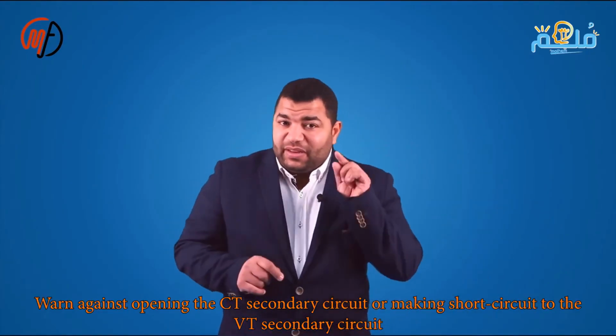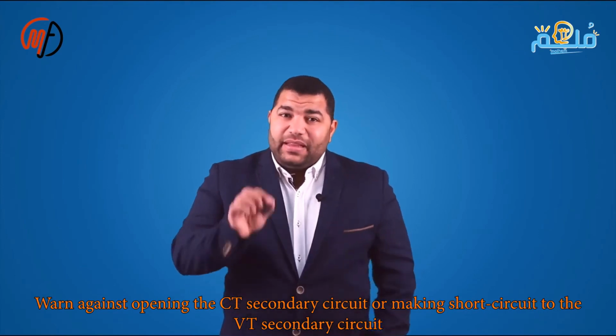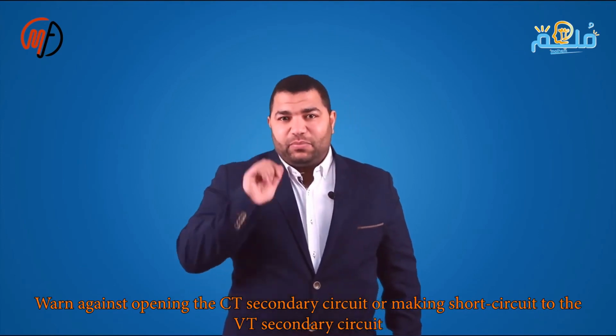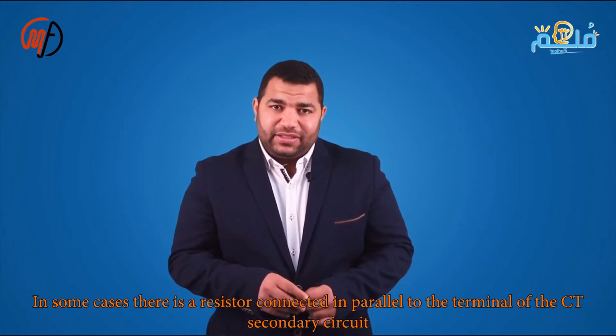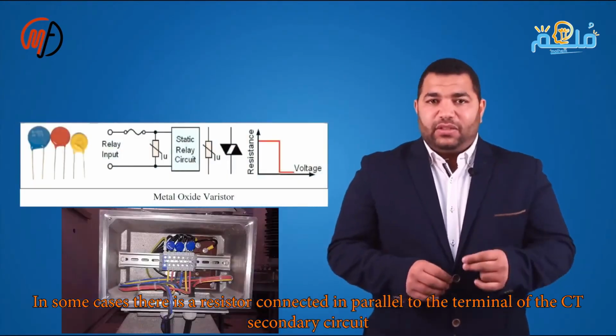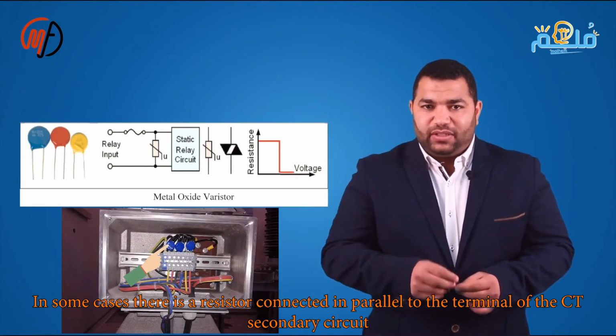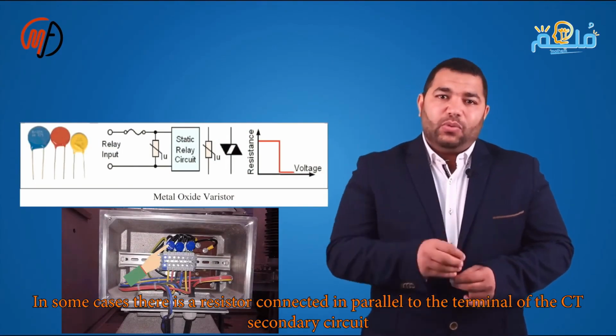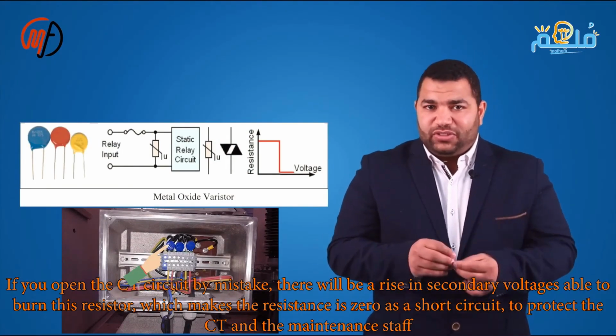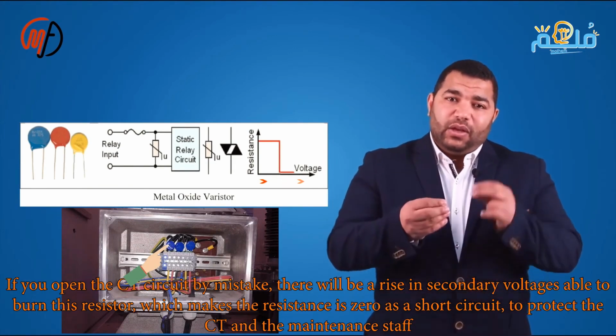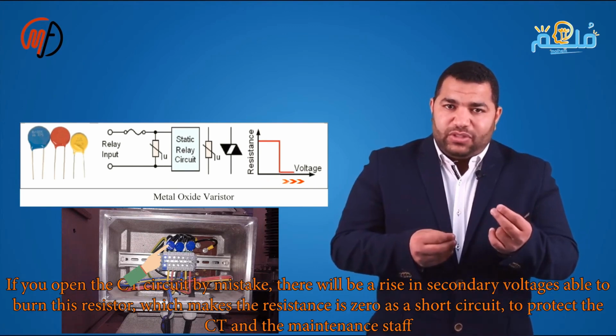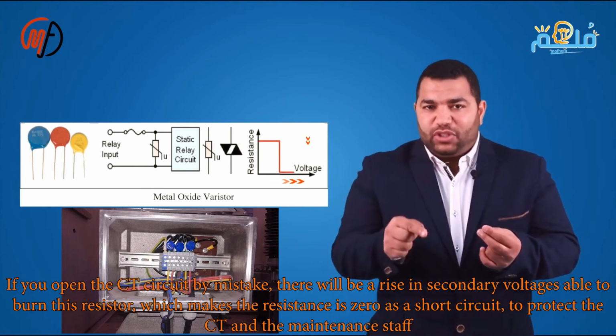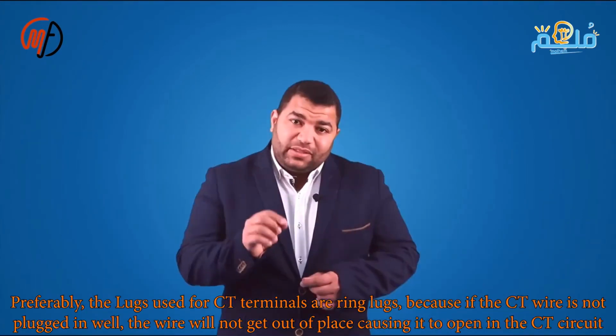A resistor parallels the CT secondary circuit for all phases. If opened, the voltage rise blows the resistor, shorting to protect the CT. Prefer ring lugs in CT terminals to prevent loosening and open circuits. During relay testing, the test switch should open the VT circuit and short the CT circuit. If the circuit opens, the voltage rise will explode the resistance, so the resistor becomes a short circuit. It's better to use ring lugs in CT terminals.